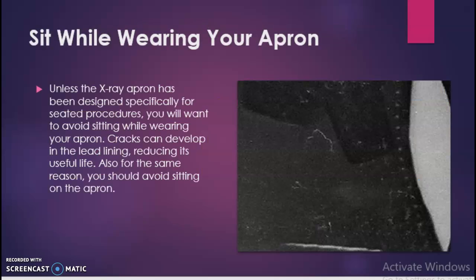When using lead, unless the lead is designed for sitting, please never sit for long periods of time with it. It can develop cracks that can then develop into uselessness of the lead apron. So if you are using a lead and you're sitting for long periods of time, please be mindful that the efficiency of the lead is being reduced.